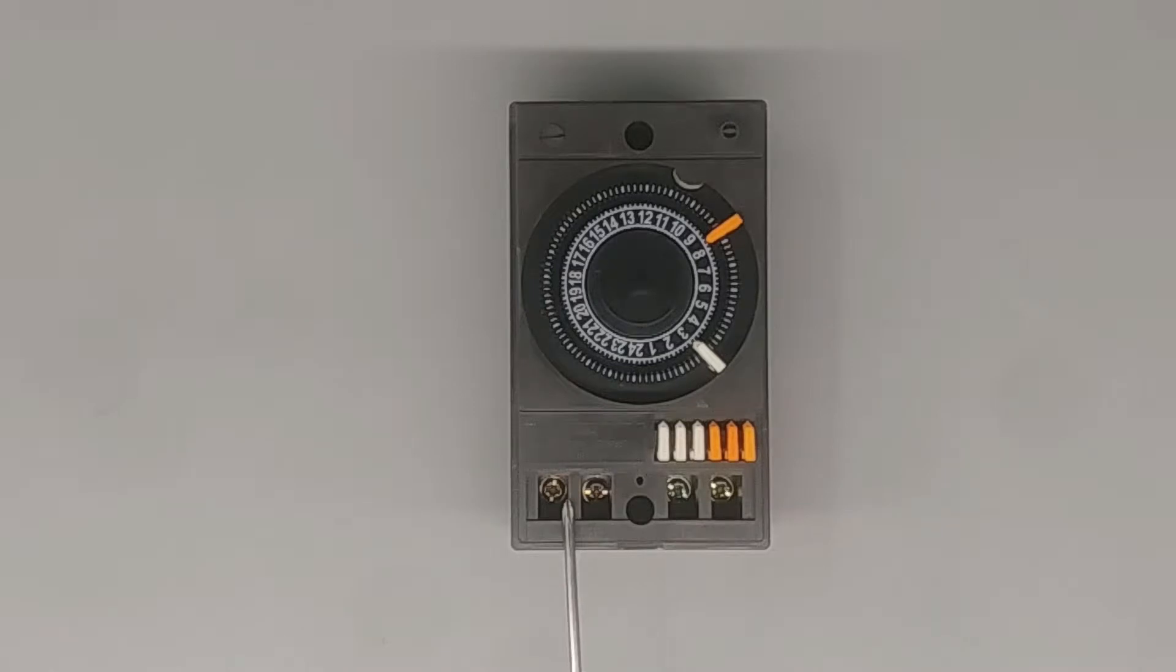This is where this one works a bit different to the normal timers. Usually with normal timers, you put the power on your live and neutral, and then this is a normally open contact which you would just put a live in and live out. But this timer does not work like that. If you've connected it like that, you'll probably get it short and the power will be tripping.